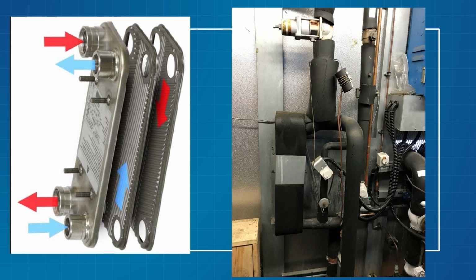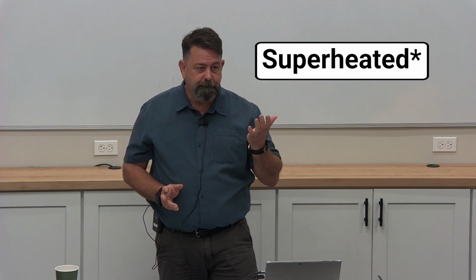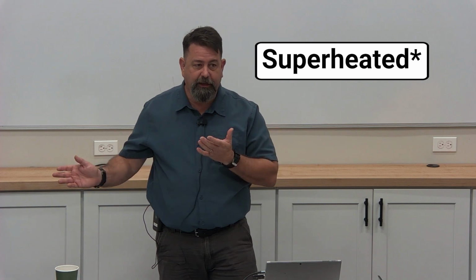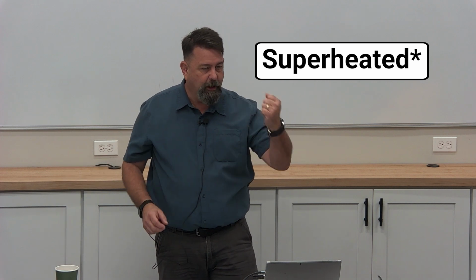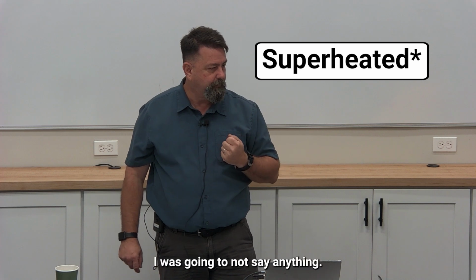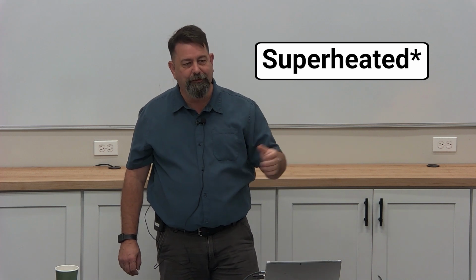It is an evaporator. That means it's gonna have a TXV, right? We're going to send liquid refrigerant into it. We're going to boil that refrigerant, change state. That latent heat exchange is going to absorb heat, and it's gonna come out as a superheated vapor. Make sense? Just like any evaporator.